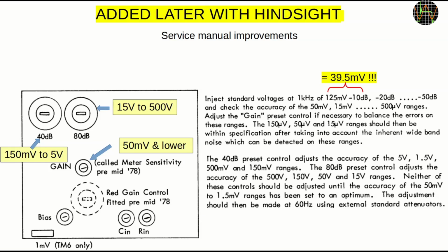A word from the future. The input resistance is not the only place where the service manual could have been improved or made clearer. I read this as that the calibration was supposed to use 125 millivolts at 1 kHz, but no, it is using 125 millivolts minus 10 dB, which is only 39.5 millivolts.